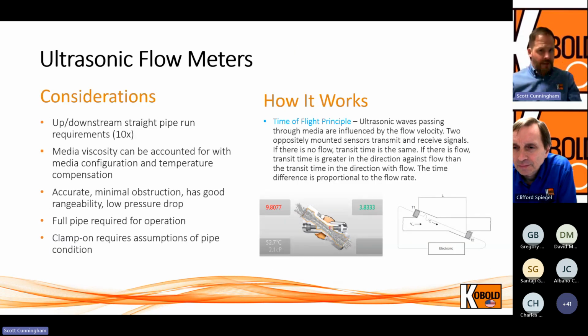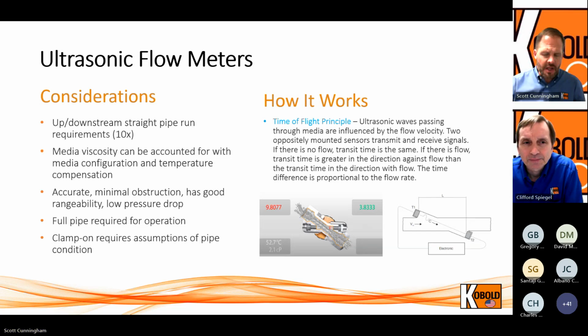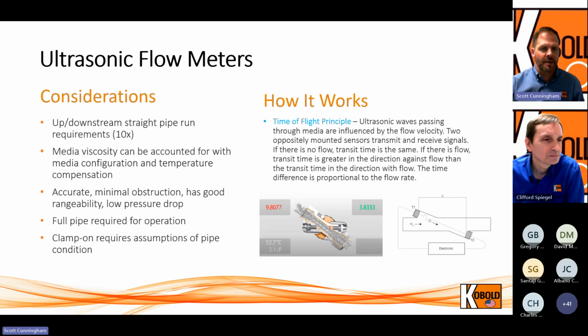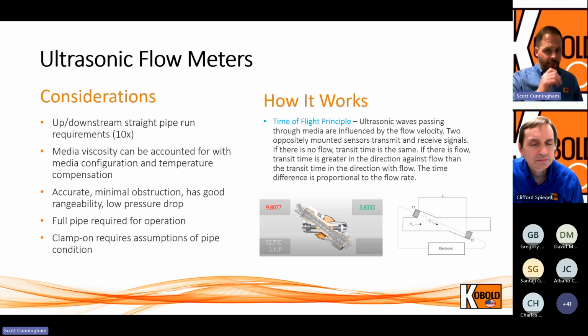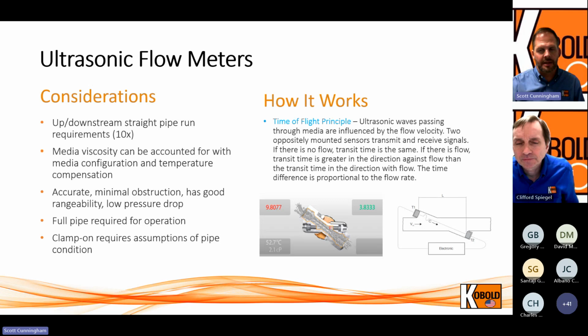So, some things to consider when you're using ultrasonic flow meters. Straight pipe run requirements: ideally, we would have a 10x upstream and 10x downstream straight pipe run. That's going to give you the highest accuracy. We've certainly implemented in cases where we don't have that, but again, if accuracy is your goal, that's best practice. Like I said, the media viscosity we can account for, and if you're using temperature compensation, that's even better for increasing the accuracy of the instrument.